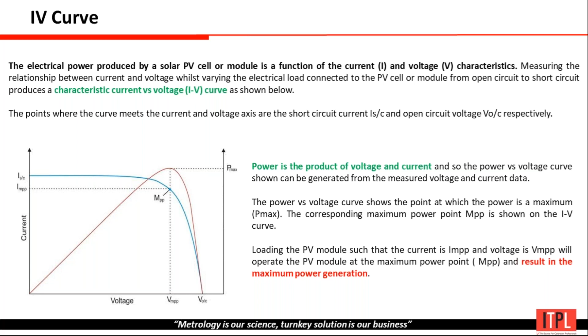Fill factor basically tells you the efficiency of a PV module. It should always be in the range of 65 to 75. If the radiation we are getting in real time is good, the temperature is also good, and our solar panel is completely clean, and in that case we test a solar panel and get a fill factor of less than 65 or less than 60, then there is a 100% possibility that there is some kind of issue in the solar panel. This might be micro cracks, a snail trail or a hot spot. Anything can happen. So this is one point, the fill factor, from which we can identify whether our solar panel is working perfectly or not.